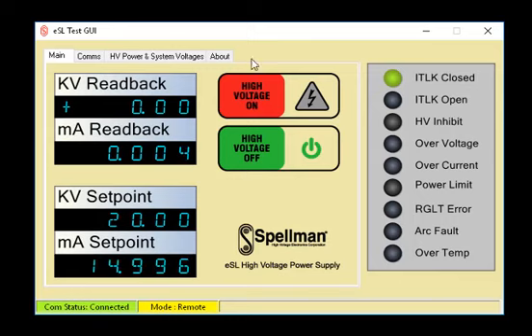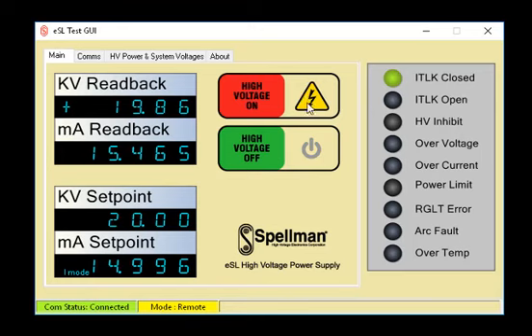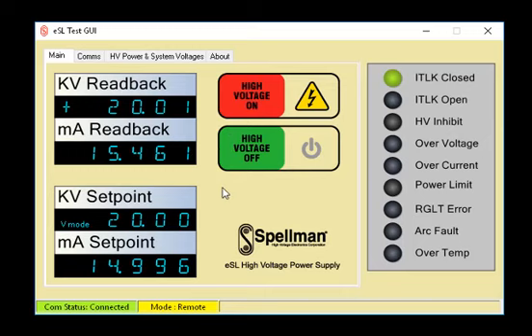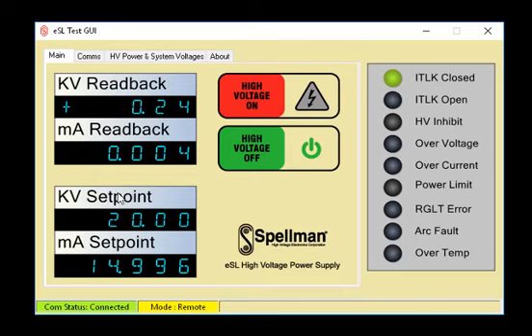High voltage on and off are controlled by these two buttons. Click the red high voltage on button and high voltage will be enabled. The warning symbol lights up yellow when high voltage is enabled. The KV and MA readbacks are now displaying the actual KV and MA being generated. Voltage mode is indicated in the KV set point window.